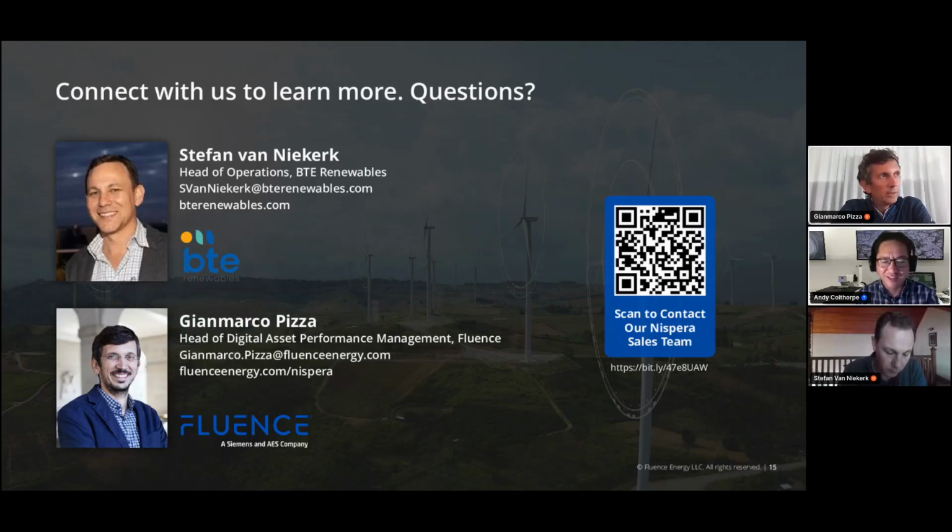Yeah, sure. Thanks, Andy. Granularity can range from some seconds, to 1 to 5, depending on the technology and on the signals which are read. A typical resolution or granularity in the wind industry is also 10 minutes, but the audience probably knows that if you want to do really advanced power curve analysis, a 10-minute granularity is not enough. It varies from technology to technology, and also from the data acquisition system which is in place, and on the signal which you are reading. Obviously, temperatures do not need the same high resolution as, for example, electrical signals.